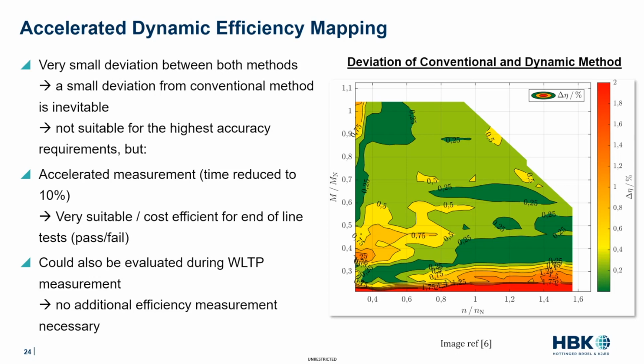So if you require the highest level of accuracy, go for the conventional method. But if you want to do dynamic efficiency mapping, for example in the context of end-of-line tests, where you want to decide is the machine okay, is the maximum efficiency of 95% realized, yes or no, then the accelerated dynamic efficiency mapping method can save a lot of time and therefore a lot of costs and resources.